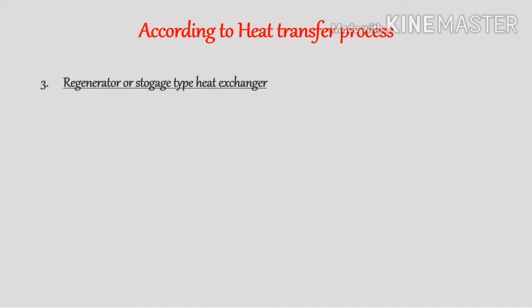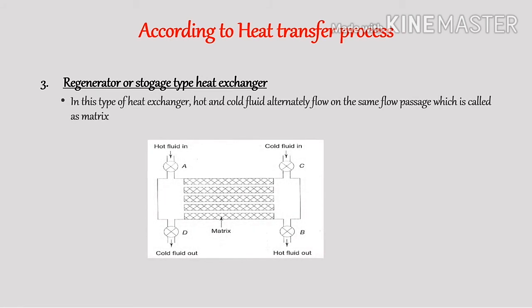The third type is the regenerator or storage type heat exchanger. In this type, hot and cold fluid alternatively flow on the same flow passage, which is called a matrix. First, hot fluid flows over the matrix, which gets heated and stores energy as thermal energy. Then the cold fluid flows over the matrix, and the matrix gives the stored thermal energy to the cold fluid. Since the matrix gains energy from the hot fluid and loses heat to the cold fluid, this type is called a regenerator.